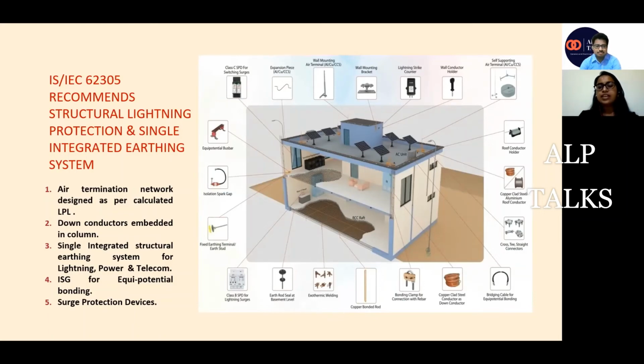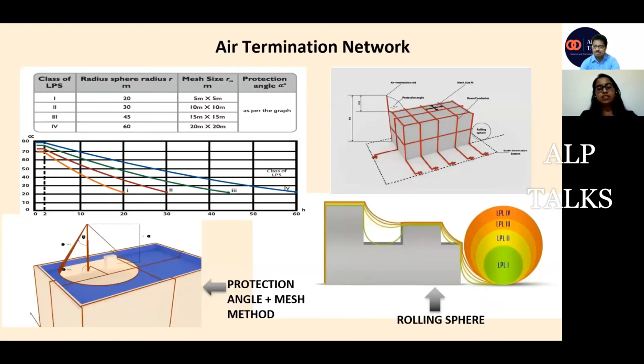It tells us that there are 3 methods of designing, and there are 2 types of installations we can go for. We can go for the structural installation, where we use the columns of our building as a natural down conductor. We just need to install the air terminals over the roof, connect them with the column rebar, and then do the earthing at the ground level or below the structure with the raft foundation. Or we can install it externally, where the down conductor comes through the wall and connects to the earthing system. Both ways we can do the installation.